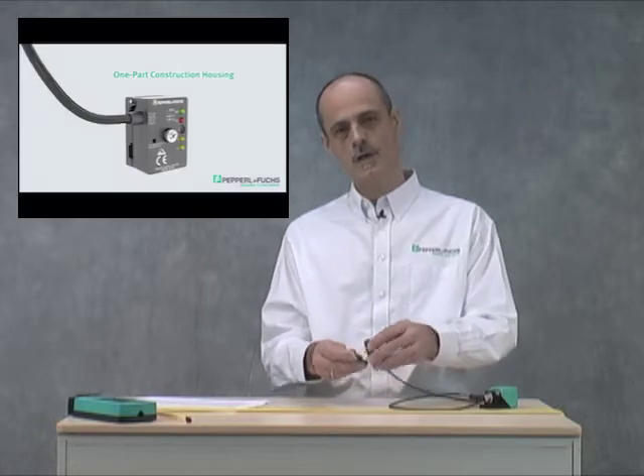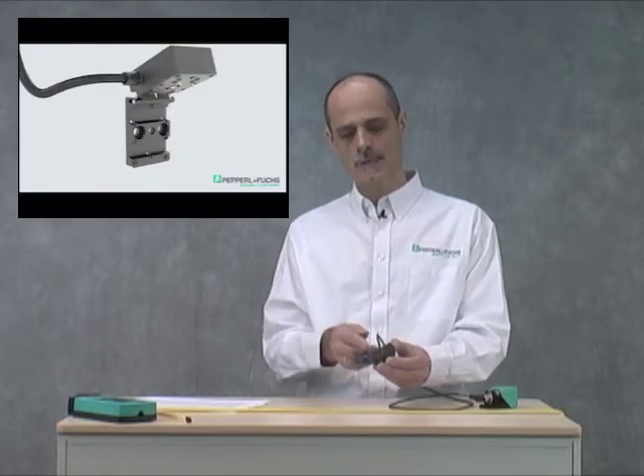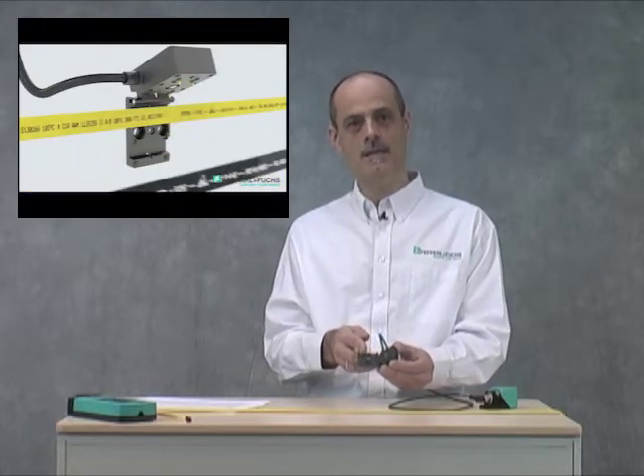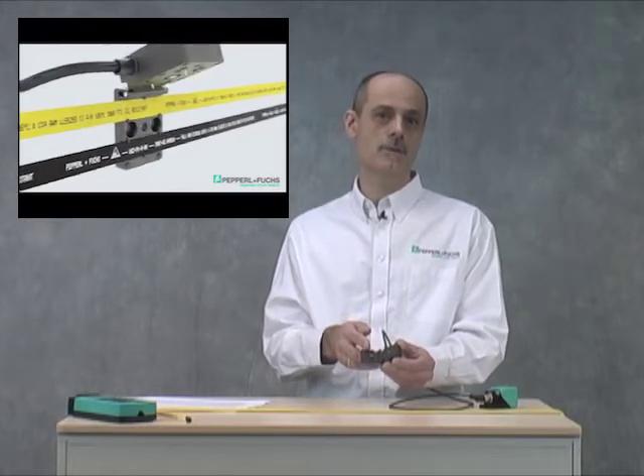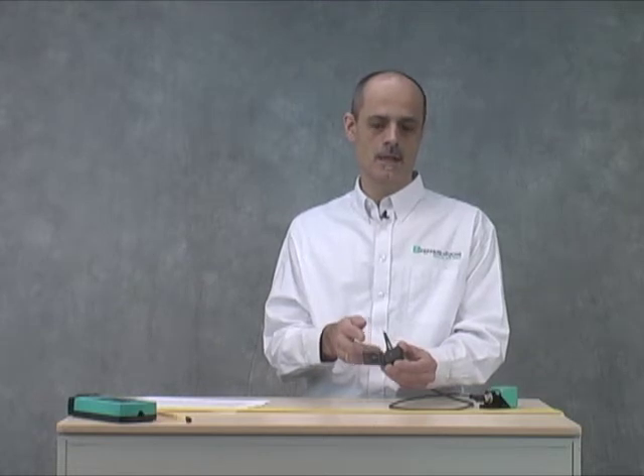Let me show you how easy it is to add the G10 modules to the network. First, open the hinged cover to gain access to the cable trays that hold the AS-i yellow flat cable and the auxiliary power flat cable. The auxiliary power flat cable is only required when a module with outputs is being used. To simplify the installation, both cable trays are always present.